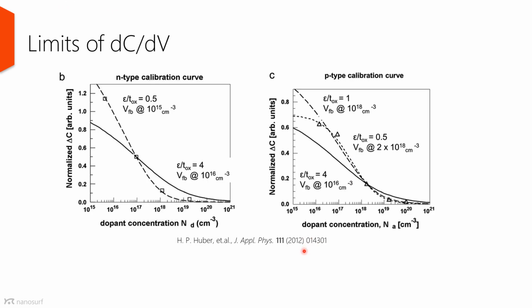Now let's talk about the limits of the dC/dV mode. What can we realistically measure with it? Here is an example of what a typical calibration curve looks like. If normalized, the dependence of the capacitance versus the dopant density looks like a sigmoid function. It saturates at both ends of the range of densities, between 10 to the 15 and 10 to the 20 atoms per cubic centimeter.